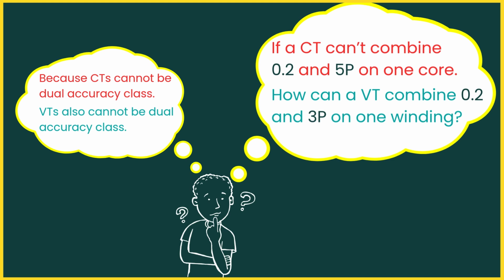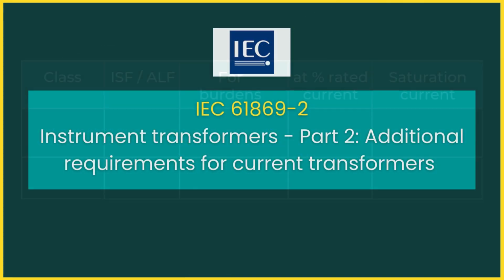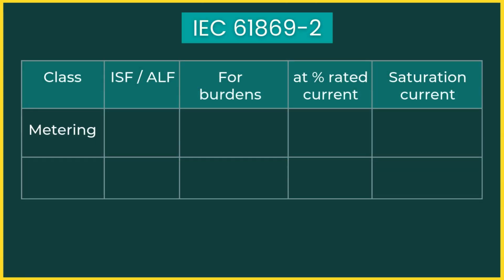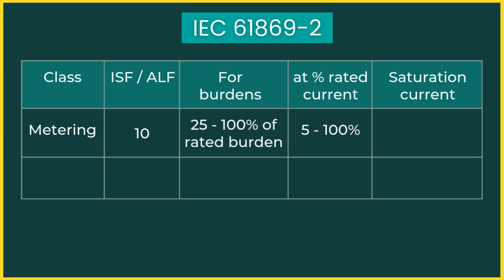To see why this belief is wrong, we must understand the difference between CTs and VTs. So first, let's understand why CTs cannot be dual accuracy class. According to IEC 61869 Part 2, a metering class CT with instrument safety factor 10 must maintain accuracy within limits for 25 to 100% of rated burden, 5% to 120% of rated current, and must saturate early, below 10 times rated current, to protect meters during faults.